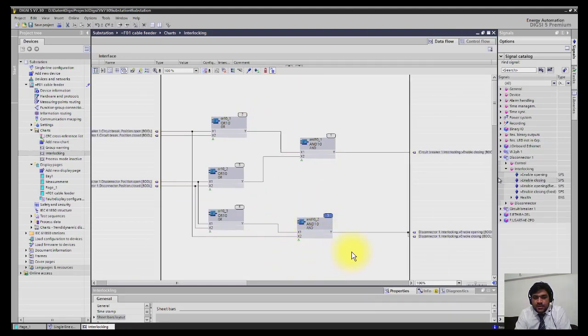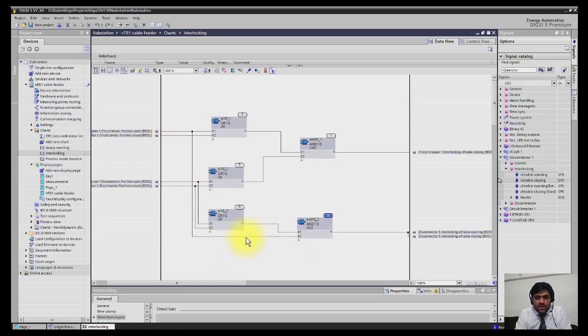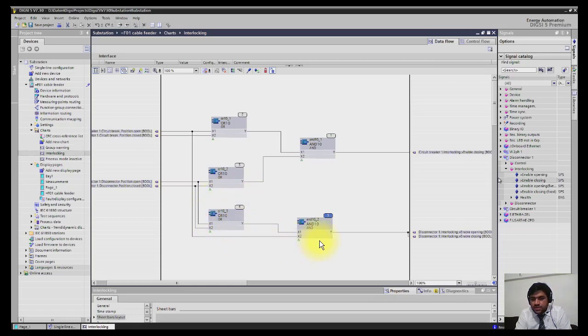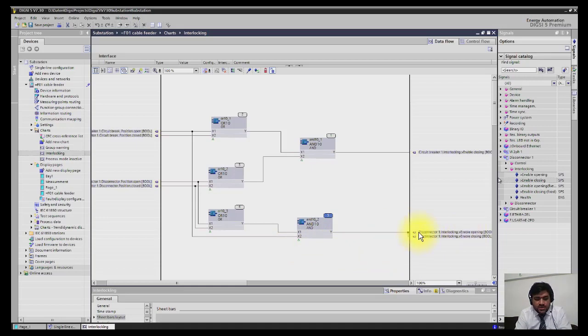In the same way you have to make interlocks for the isolator. The isolator can only be operated if the breaker is in open position. Link it to X2. The isolator should have a very clear status, either it should be open. If it is intermediate you should not be able to operate the isolator. I have just connected it to enabling open label and enabling close. This is the way how it works here.